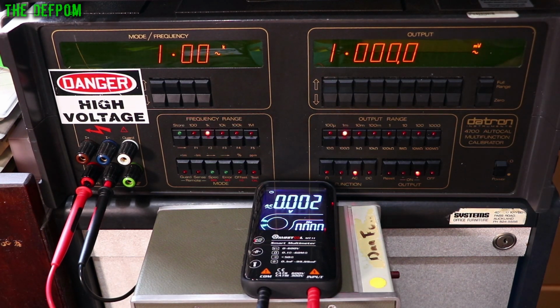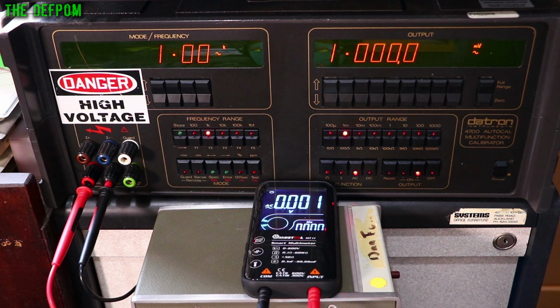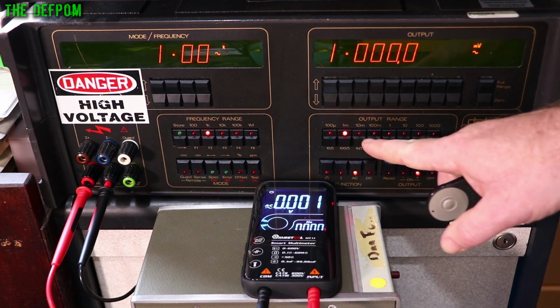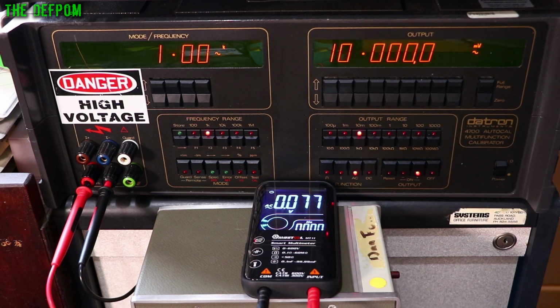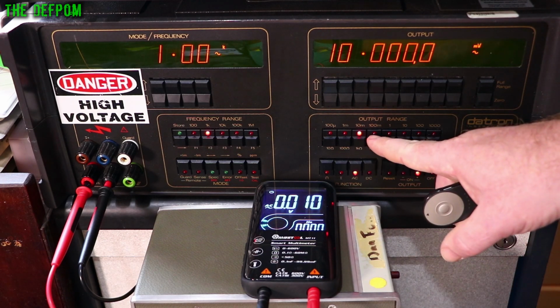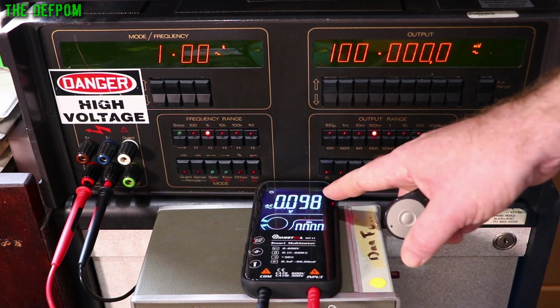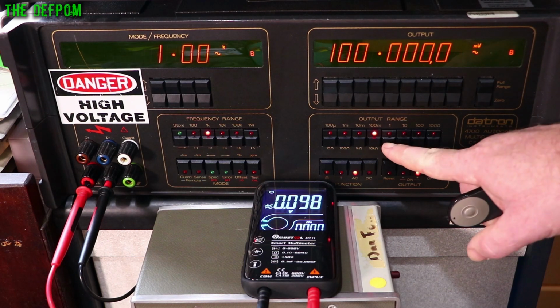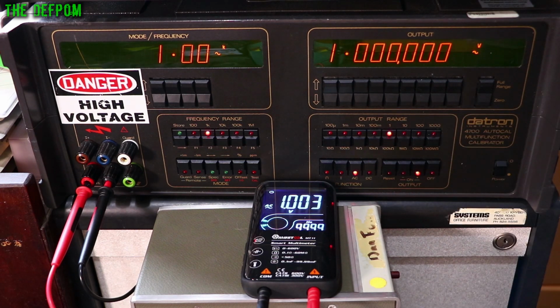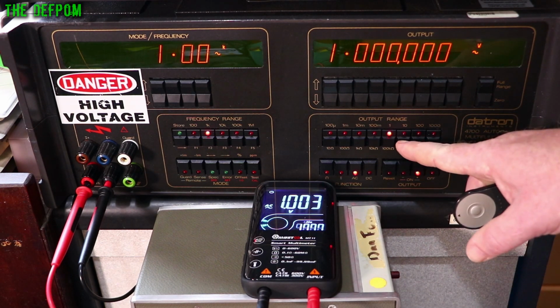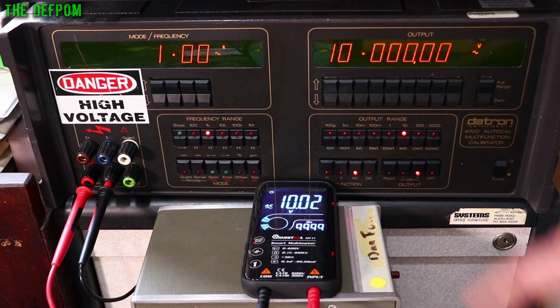It's got some interesting specs here. It says frequency range 1 kHz below 10 volts, 6 kHz above 10 volts, which is interesting. Anyway, we're doing 1 millivolt right now and it's counted as 1 millivolt, so that's good. 10 millivolts, bang on. Again, this is all manually ranged, not auto ranged. So 100 millivolts is slightly off there, a couple of counts. 1 volt, a few counts out. Still within spec. 10 volts, a couple of counts out.